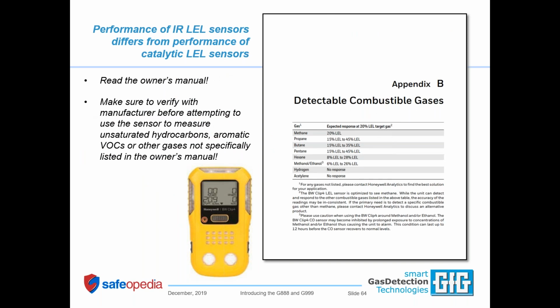Now here, I'm simply looking at an excellent product from one of our honored competitors. I've gone to the owner's manual of the Clip 4, and I've pasted in a copy of the page. So what does the page say in case you can't read it? I will read it for you. The notes include this one. The BW Clip 4 LEL sensor is optimized to see methane, period. While the unit can detect and respond to the other combustible gases listed in the above table, the accuracy of the readings may be inconsistent. If the primary need is to detect a specific combustible gas other than methane, please contact Honeywell Analytics to discuss an alternative product. And in the above table, they tell you those pitiful few gases that they are willing to admit the sensor is able to measure.